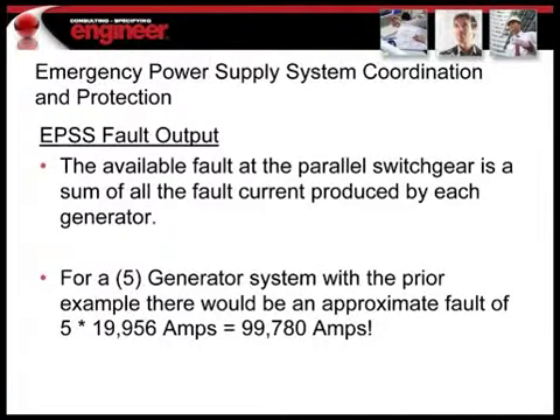Now, the important thing to consider from a multi-generator fault is that you may have all generators operating at one time and all contributing to the bus. So if you had a downstream fault south of the generator breakers, you would combine the fault from those multiple generators. In this case, if you had 5 generators of this type on one system, you're producing almost 100,000 amps of available fault current. Now, I'm not including wire losses and I'm not including motor contributions in that. As a general rule of thumb, you're looking at a good amount of fault, which, as you'll see Dean get into in the next slides, does affect the size of your ATSs and the AIC ratings of those units.